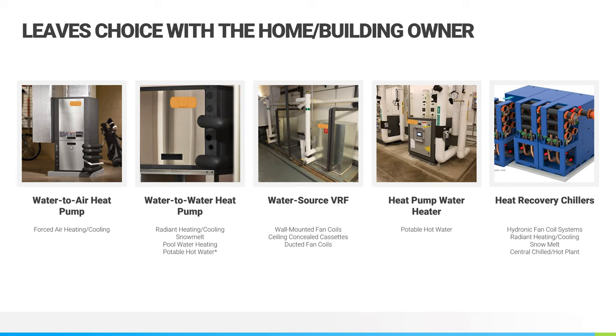So if they're used to that forced draft furnace, then they can go with your traditional water to air heat pumps. If they're looking for something like radiant heating or cooling, water to water heat pumps can be done. If they like wall mounted mini split fan coils or the concealed look of VRF, they can go with a water source VRF system that provides the same exact benefits.